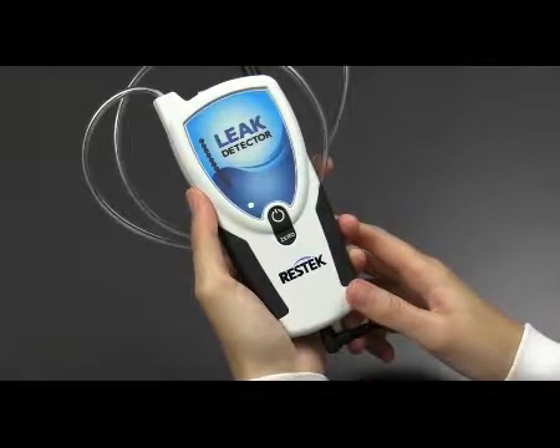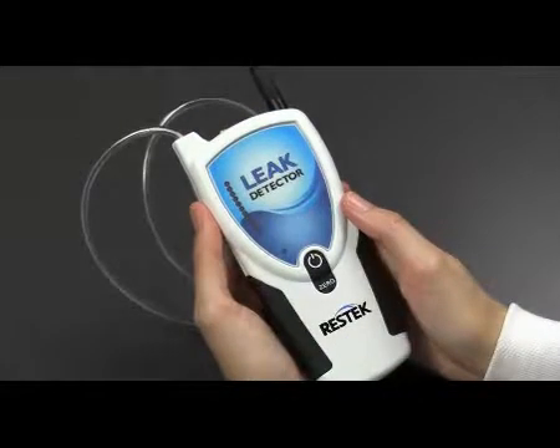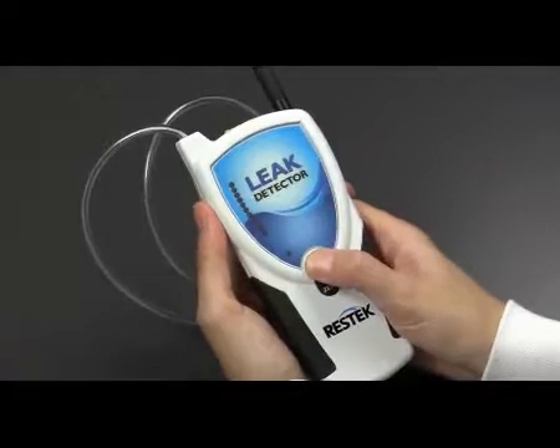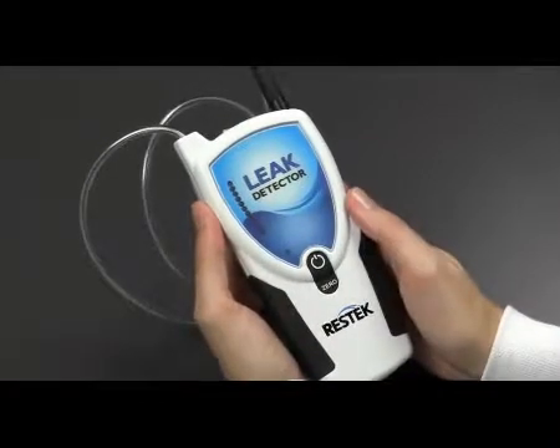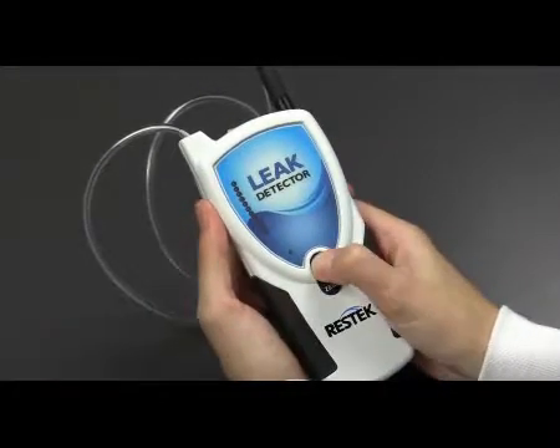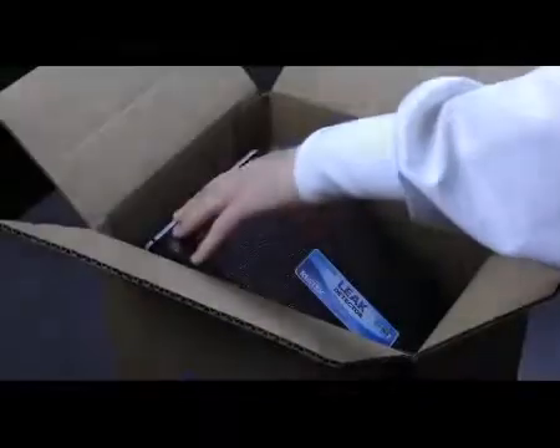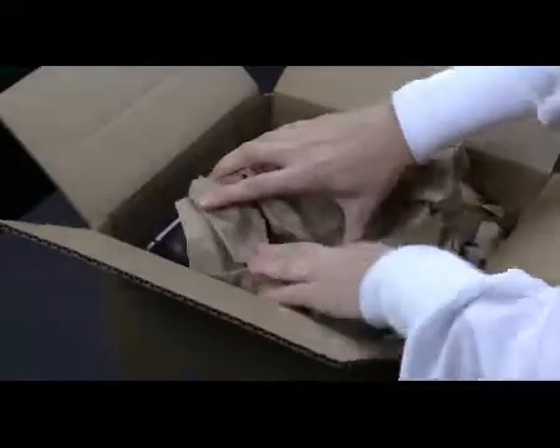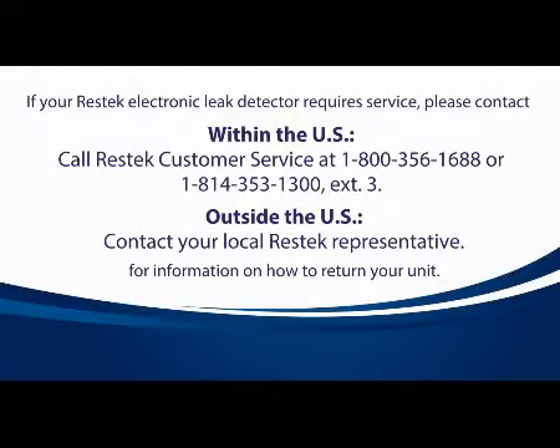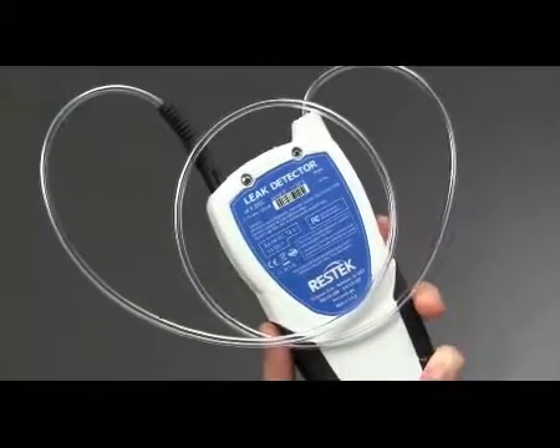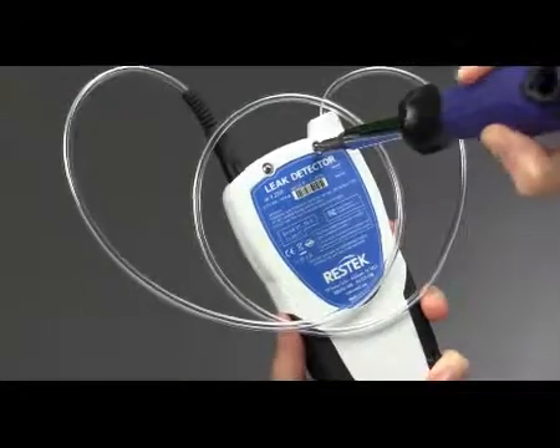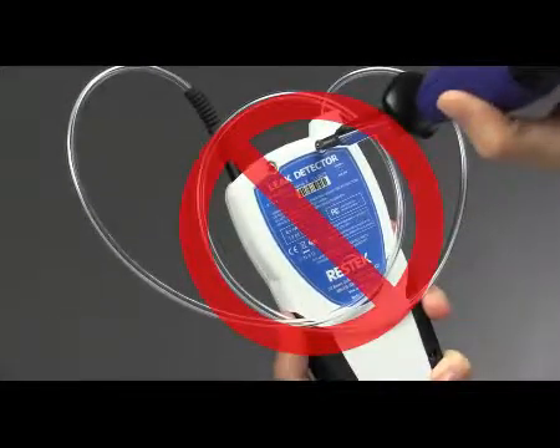unit more frequently. Proper battery charging is critical. Like with many electronics, the battery can drain to a point where the unit's protection circuit will not allow it to recharge. If this happens, a battery replacement will be necessary and must be performed at the factory. Contact Restek or your representative for battery replacement service. Opening the case or tampering with the internal parts of your Restek leak detector will void the warranty.